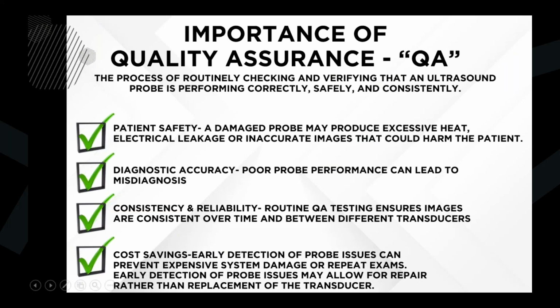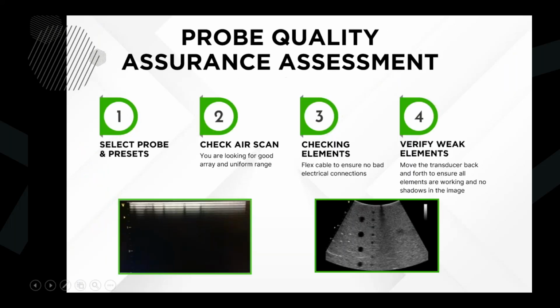All right. So the first thing I say we do for our transducers is an air scan. When we complete an air scan, we just basically select the probe. We put the probe on the ultrasound system, select it, select the preset, and check the air scan. This is the near field. This is the array of the transducer here. What we're looking for is uniformity across the entire transducer. This particular one, you can see dropouts or shadows, and so this air scan would fail.